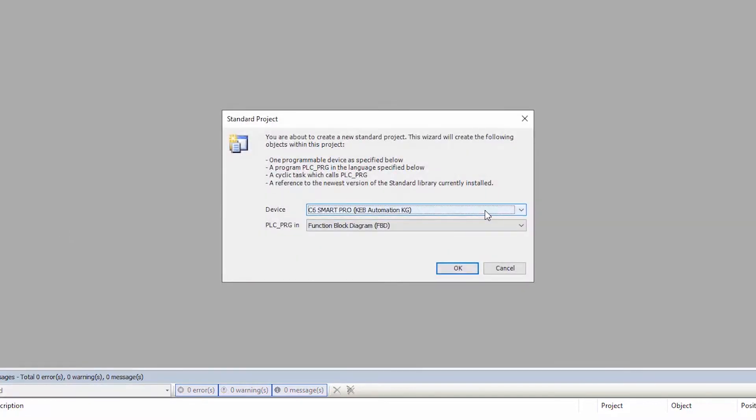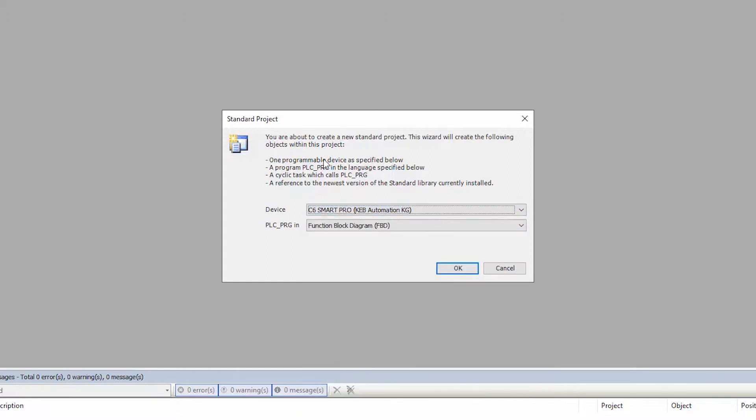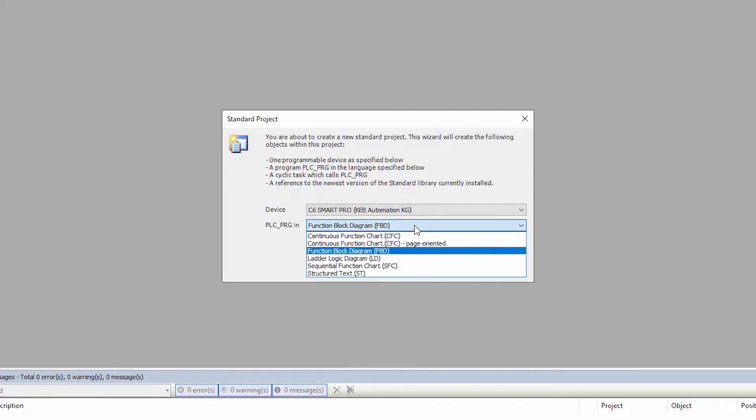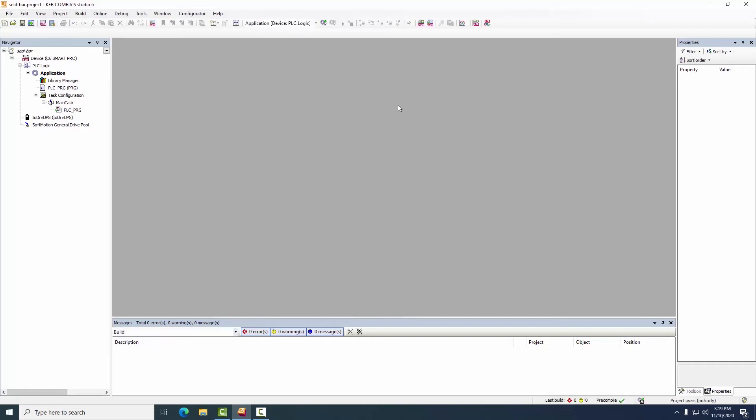The control platform we're going to demonstrate is our C6 smart control which is a DIN mount product and we're going to use the pro level performance which is required for soft motion or coordinated motion. The main PLC PRG program I'm going to choose function block diagram as this will be a fairly easy and straightforward way of showing the function blocks that we use for this application.